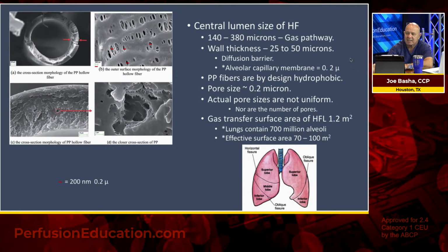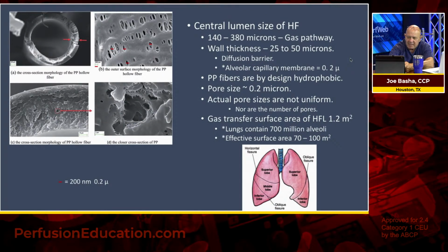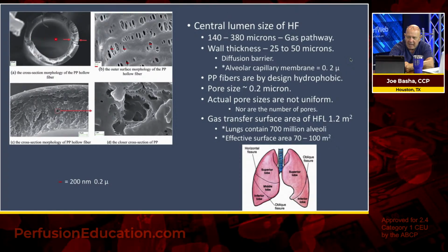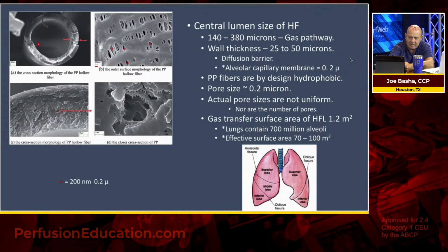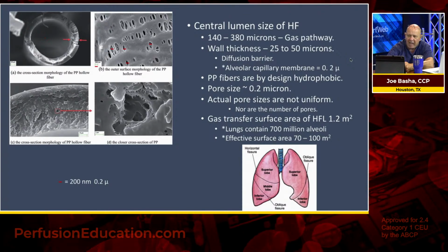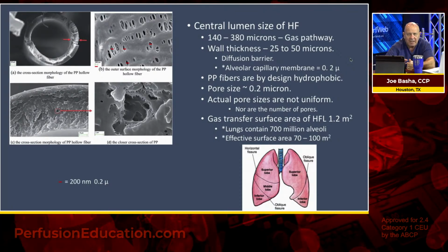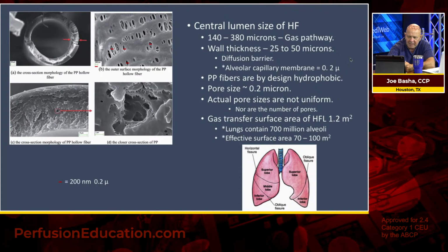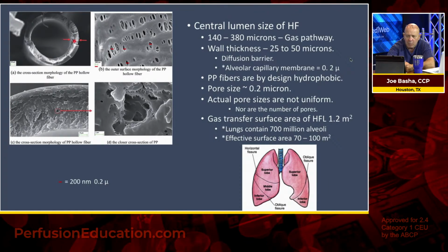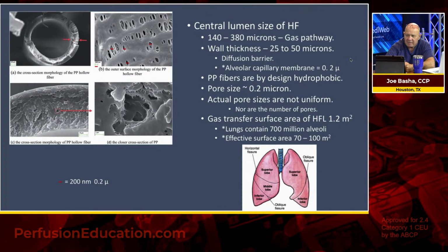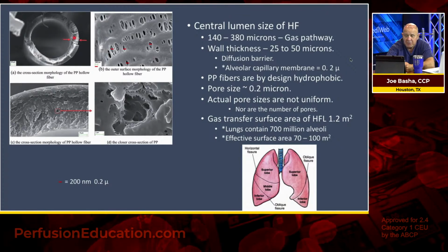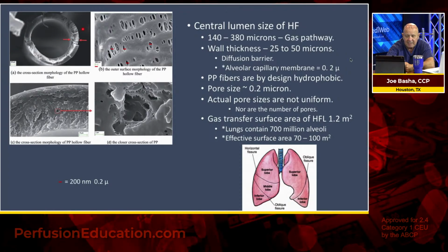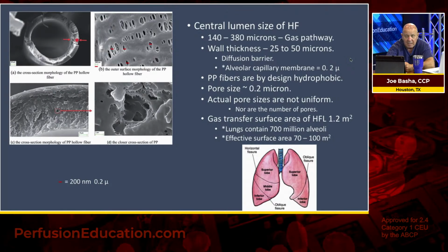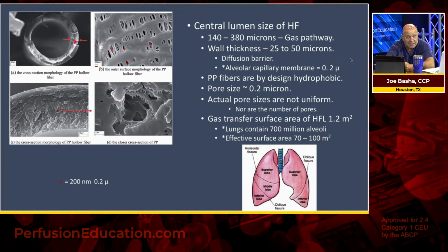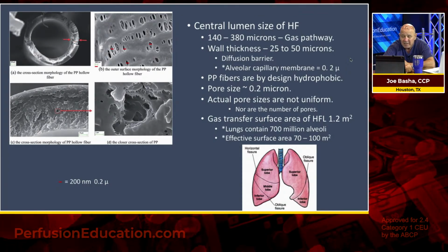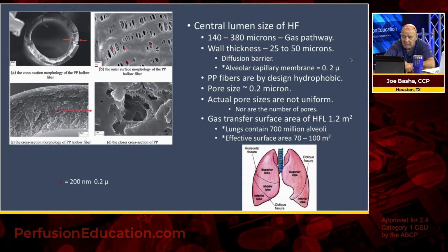So central lumen size of hollow fiber, and that's going to be this section between here and here. The tube itself, the lumen of the tube, not the pores, which is the gas pathway, is about 140 to 380 microns. The wall thickness, which you see right here, is between 25 and 50 microns. And that's referred to, so you know, as your diffusion barrier, because you've got gas on this side, blood's going to be on the outside, and it's got a 25 to 50 micron separation. And that is a significant diffusion barrier when you consider the alveolar capillary membrane is only 0.2 microns. So a very significant difference there.